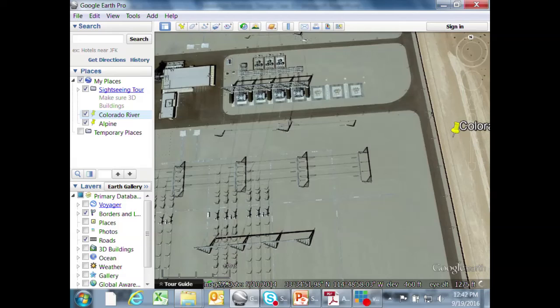These structures are, my recollection, about 90 to 95 feet tall. Again, you have to span over the main buses. They put them just behind the transformers, so the jumpers drop down to the primary bushings. But on the secondary bushings, you have bus supports that train the conductors out, and then you connect up to this side. This is the tertiary bus.